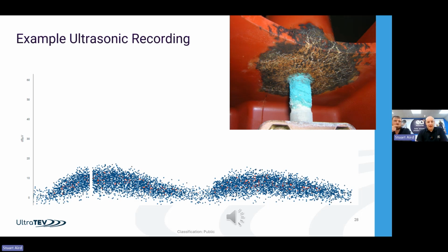And we can see the clear phase plot as well recorded on this. We can see two areas raised, two groups of activity, 180 degrees apart, indicating clear surface partial discharge characteristics. This picture in the top corner is a stock picture, but it's the same type of switchgear, and probably a problem they'll find when they open up that board.